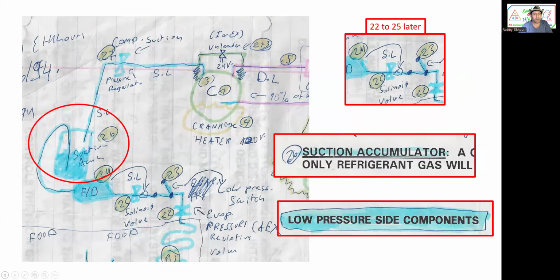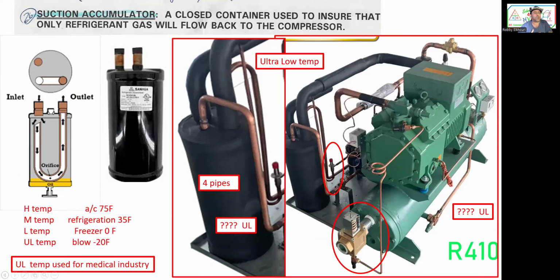Suction accumulator is next. The suction accumulator's main job is to make sure no liquid refrigerant goes to the compressor because we don't want slugging. You're not going to see it in air conditioning, it's not needed, and you're not going to see it in refrigeration. It's only for freezers, for low temp and ultra low temp. Now, another small lesson here. We have high temp air conditioning, temperature 75, boiling point 35. Medium temp refrigeration, temperature 35, boiling point 20. Freezers, 0 degrees, boiling point or evaporation temperature at -10. And we have ultra low temperature, below -20, for the medical industry.